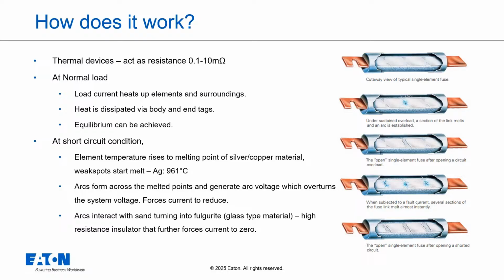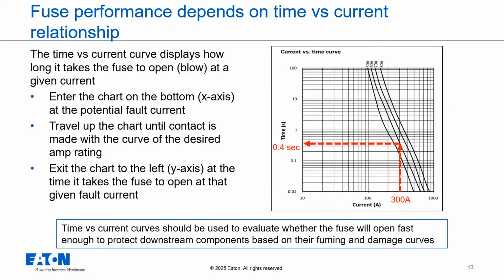This graph, the time current curve, is key to understanding how a fuse performs. It shows you how long it takes for a fuse to open or blow at a specific current level. To read it, you find the potential fault current on the bottom, the x-axis. You move straight up until you hit the curve for the fuse's amp rating you're looking at. Then you move left to the side, the y-axis, to see the time it takes for that fuse to open at that fault current. For instance, if you have a 60 amp fuse and the fault current hits 300 amps, it will take 0.4 seconds to open based on the curve. We use these curves to check coordination, making sure the fuse opens fast enough to protect the components downstream.